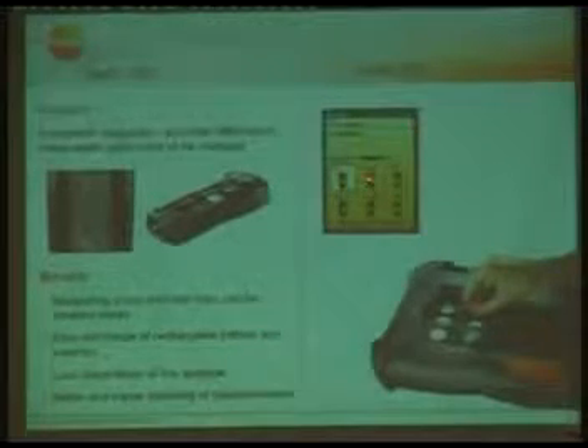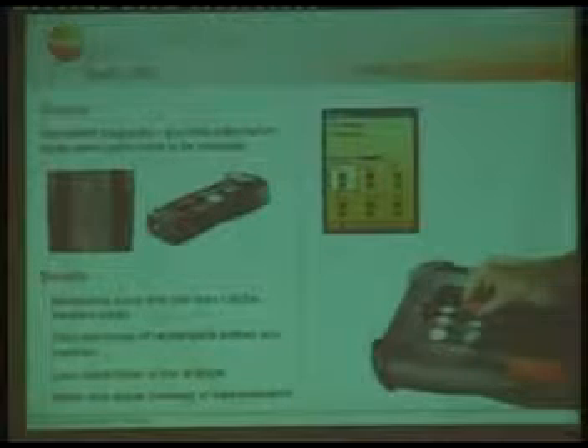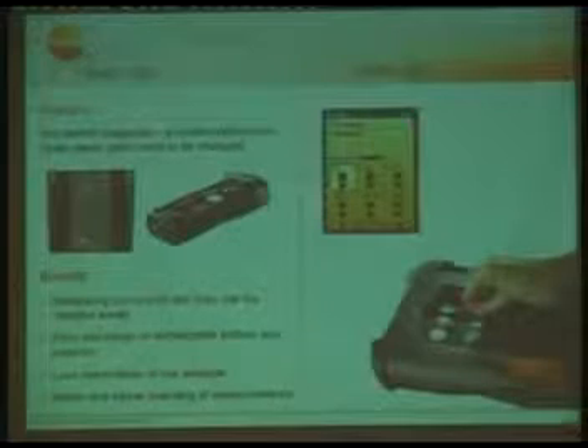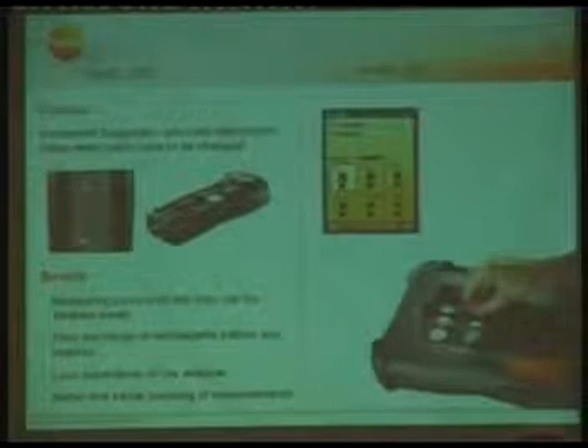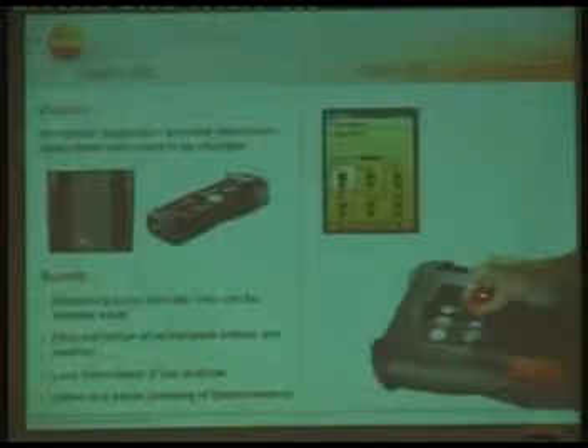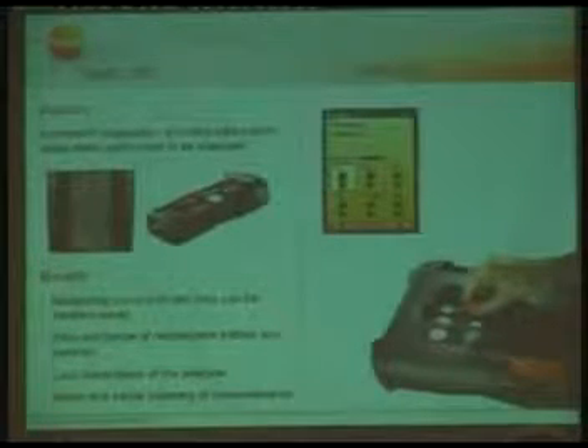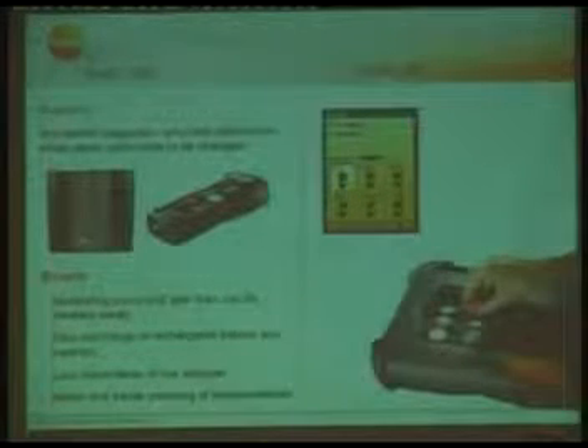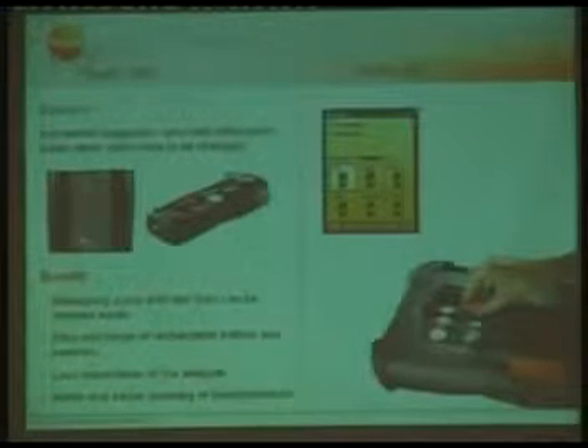Please be aware of a spare part or a spare sensor, and if it's red, you have to change the sensor. But this is very easy, an overview for you to figure out, okay, I can perform my measurement or I have to be aware of a spare part. And of course, it's very easy to replace the sensor in both instruments, just removing the hoses, put out the old sensor and put the new sensor in, connect the hoses again, and then you can continue the measurement.